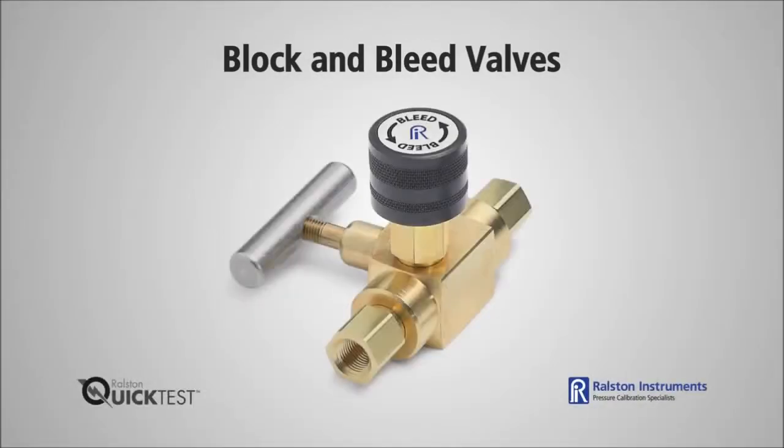The Ralston block and bleed valve comes in a variety of configurations with NPT and female and male QuickTest ends. Valves come in both brass and stainless steel, so if you have a chemical compatibility issue, such as sour gas, we recommend using a stainless steel valve.